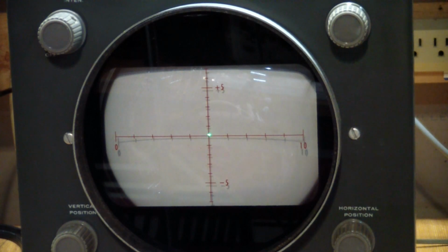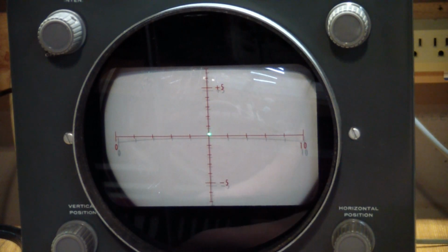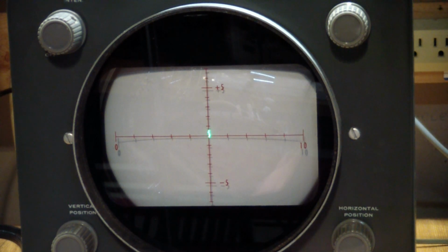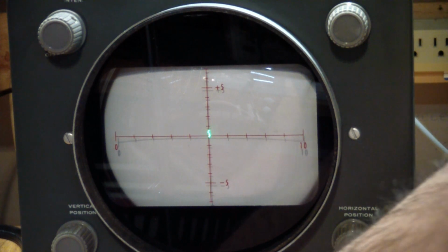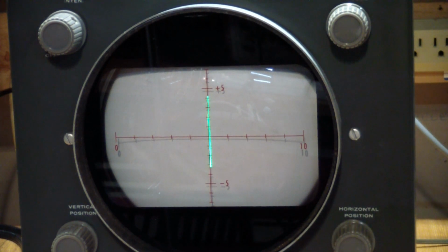Okay. So next, the way we do it is there is a calibration output of a 1 volt sine wave that's derived from the AC input. So over here it's running at 60 Hertz. And the way to test the vertical amplifier is to turn up the vertical gain. Now the vertical input is set at the 100 multiplier, so let's bring that down, and we get a somewhat straight line.